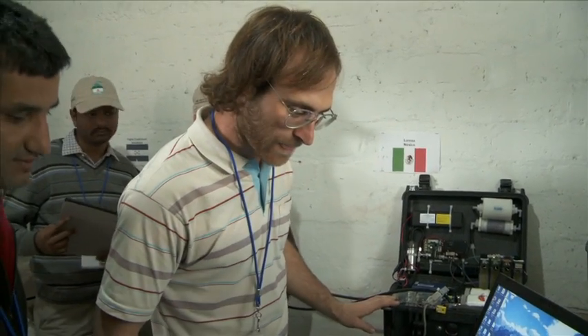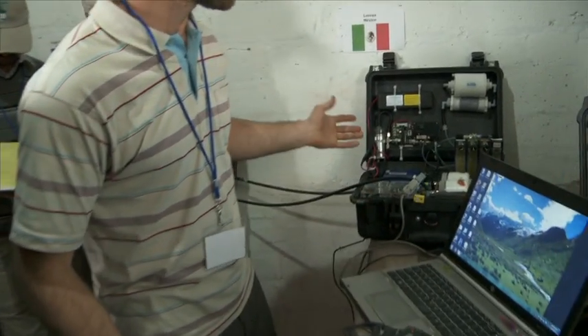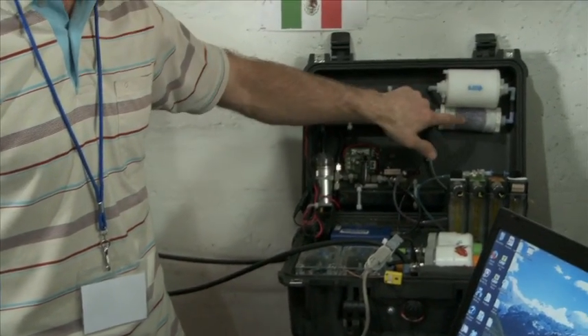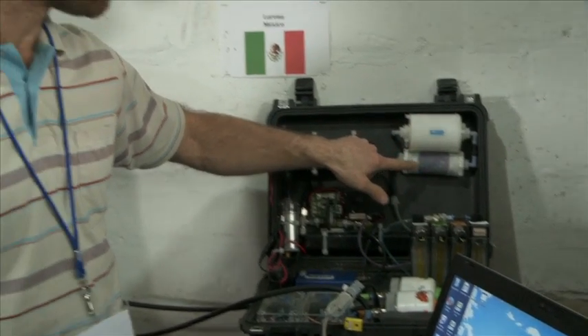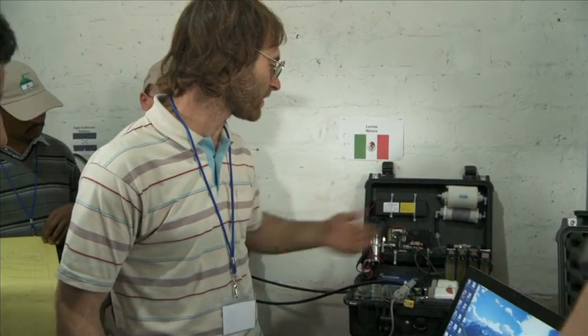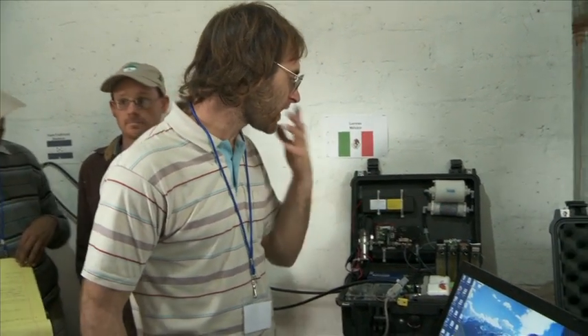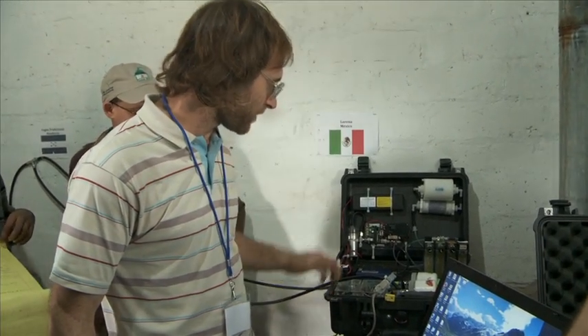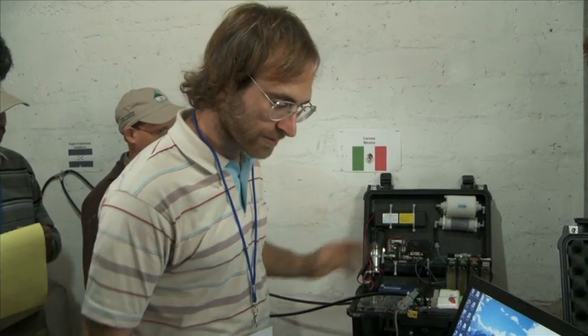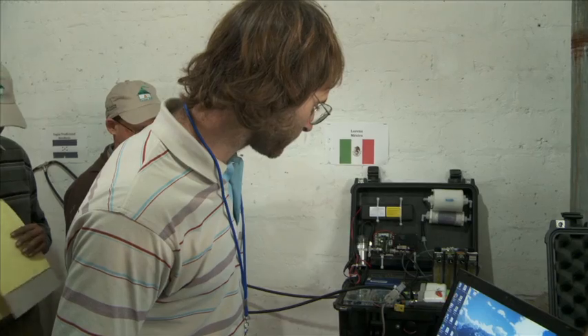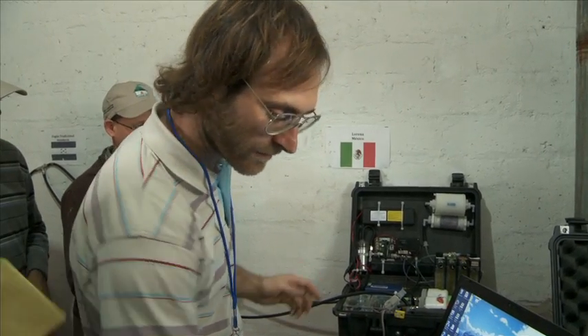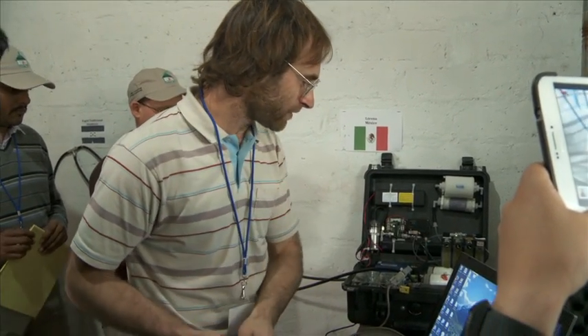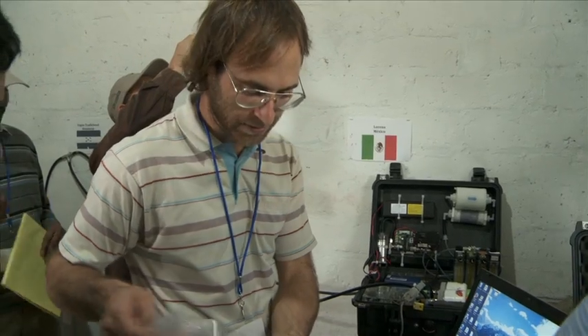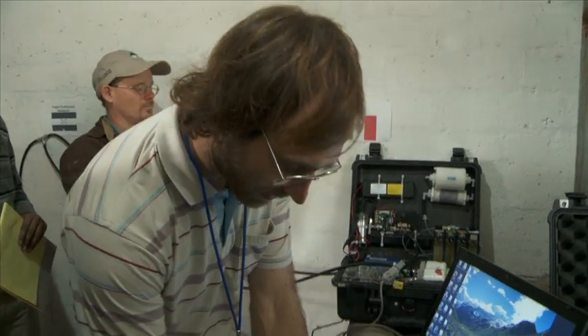So the first thing you do is, the day before, the night before, you make sure the desiccant is blue, you know that it's not expired. That dehydrates the air. And then we also charge the batteries, just regular maintenance stuff. And then, before the test, we have to load the filters in. We run 2 filters, but today we're just going to use 1, just for simplicity.